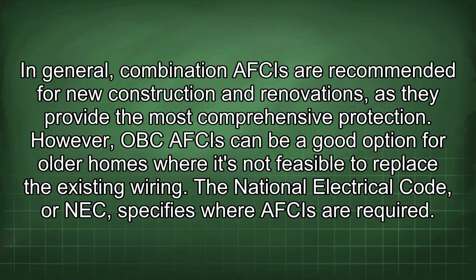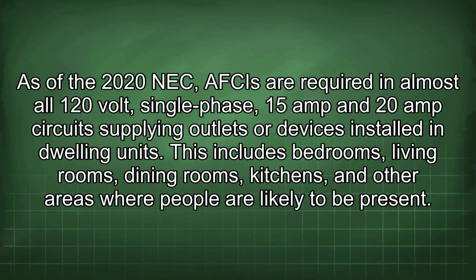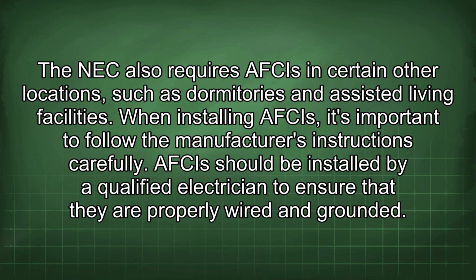The National Electrical Code, or NEC, specifies where AFCIs are required. As of the 2020 NEC, AFCIs are required in almost all 120-volt single-phase, 15-amp and 20-amp circuits supplying outlets or devices installed in dwelling units. This includes bedrooms, living rooms, dining rooms, kitchens, and other areas where people are likely to be present. The NEC also requires AFCIs in certain other locations, such as dormitories and assisted living facilities. When installing AFCIs, it's important to follow the manufacturer's instructions carefully. AFCIs should be installed by a qualified electrician to ensure that they are properly wired and grounded.